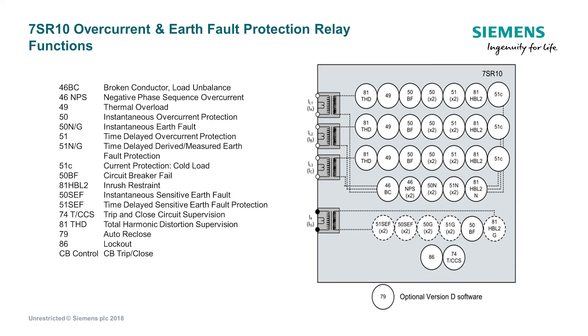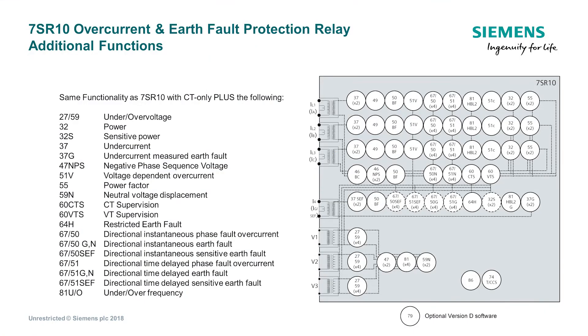In terms of protection functionality, the 7SR10 provides three phase overcurrent and both measured and calculated earth fault. Therefore the relay can provide phase overcurrent, earth fault and sensitive earth fault in one device. With the addition of voltage transformers, the 7SR10 not only provides directional overcurrent and earth fault, but a number of additional functions. These include under and over voltage, under and over frequency, and directional power protection.